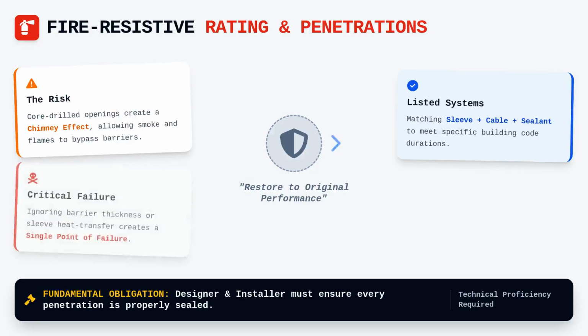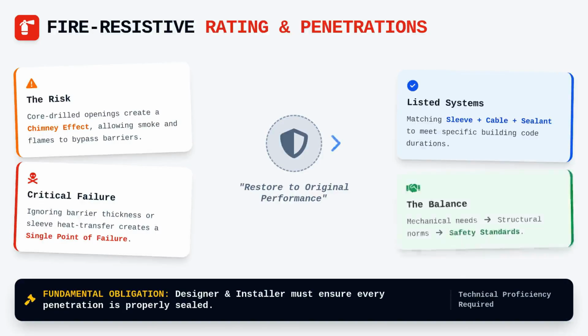If we fail to account for the thickness of the barrier or the heat transfer properties of the metallic sleeve, we risk creating a single point of failure that compromises the safety of the entire floor. Achieving technical proficiency in this area requires a balance between mechanical requirements, strict adherence to structural norms, and an uncompromising commitment to fire safety standards.